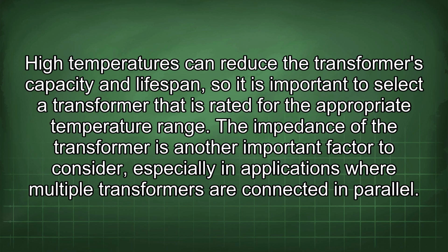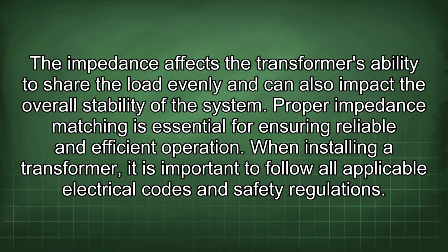The impedance of the transformer is another important factor to consider, especially in applications where multiple transformers are connected in parallel. The impedance affects the transformer's ability to share the load evenly and can also impact the overall stability of the system. Proper impedance matching is essential for ensuring reliable and efficient operation.